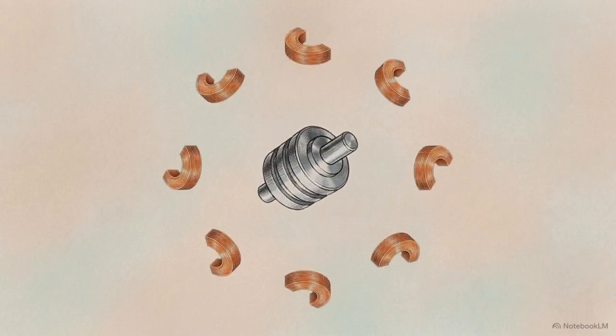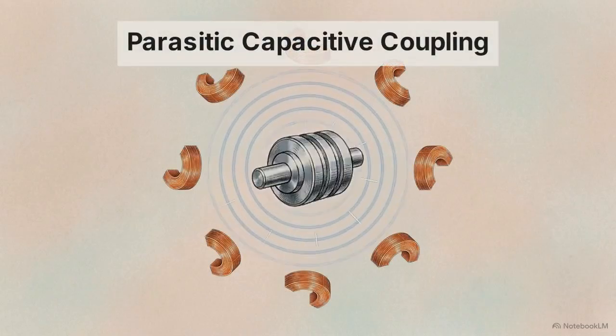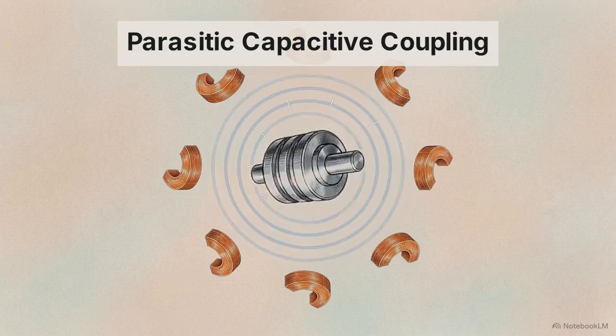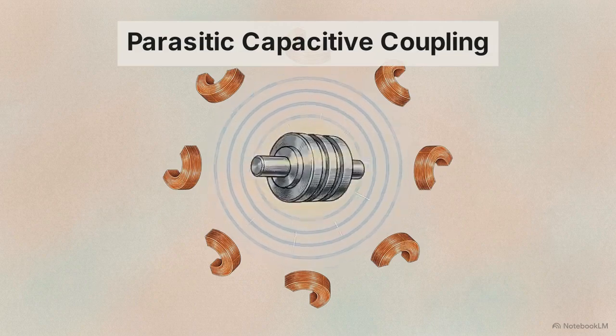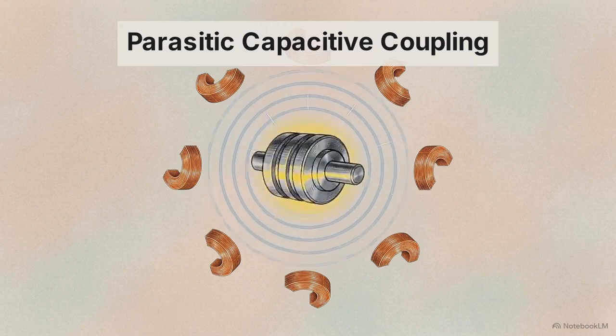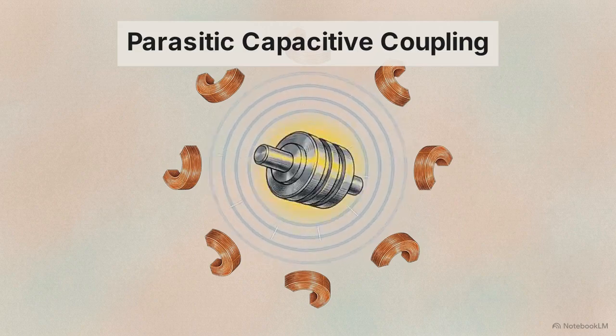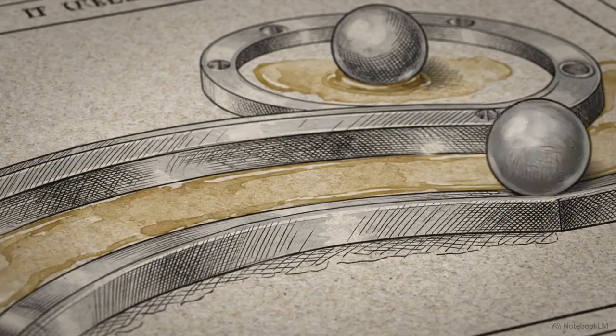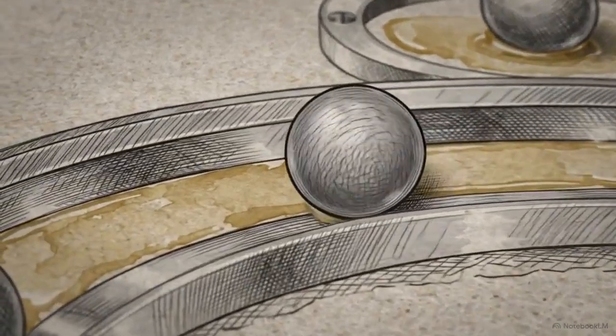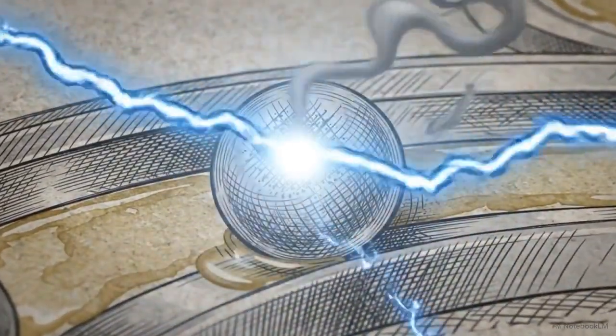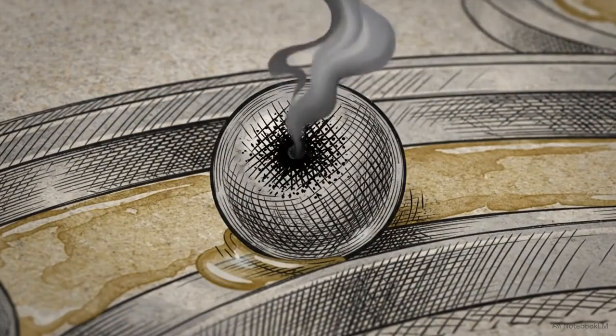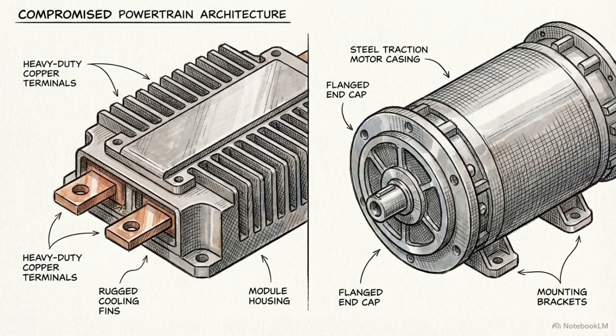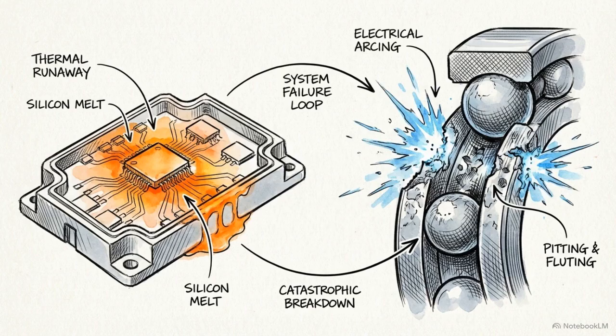Even worse, the high-frequency common mode voltage from the inverter creates a parasitic capacitive coupling effect. This induces a dangerous high-frequency voltage directly on the spinning rotor shaft. This shaft voltage violently searches for ground. It arcs directly through the thin oil film of the motor bearings, creating destructive microcraters in the steel. In legacy systems, the silicon carbide powertrain faces a terminal failure loop. Concentrated heat overwhelms cooling, while high-frequency transients electrically machine the motor bearings to death.